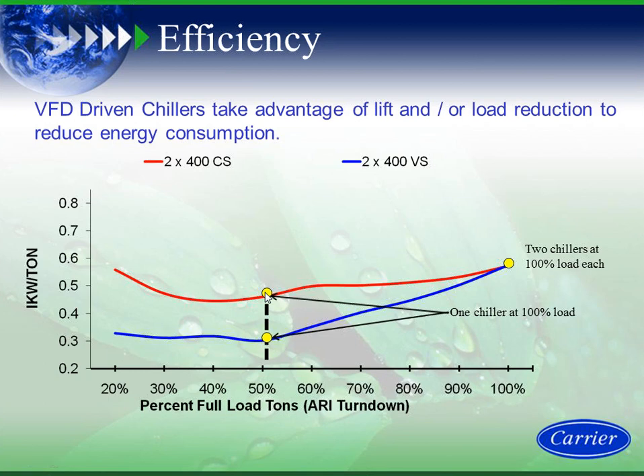And it really comes back to the point where we're looking at lift and load reduction, right? As far as lift, at that 50% building point, I have cold condenser water. Because I have cold condenser water, I reduce lift. The VFD on a centrifugal chiller is a lift reducing device. Therefore I'm able to have better kW per ton with the chiller plant at 100% load with cold tower water. That's why the blue variable speed drive blue line that represents 2 400-ton variable speed centrifugals is better.